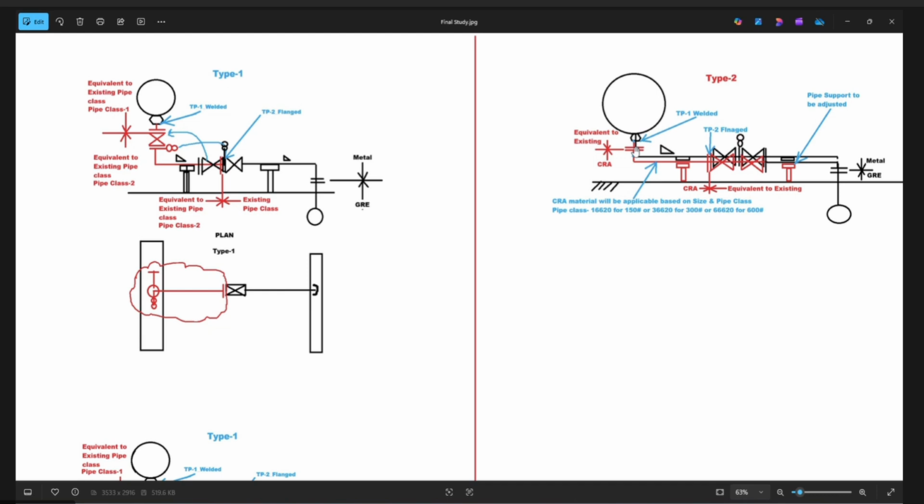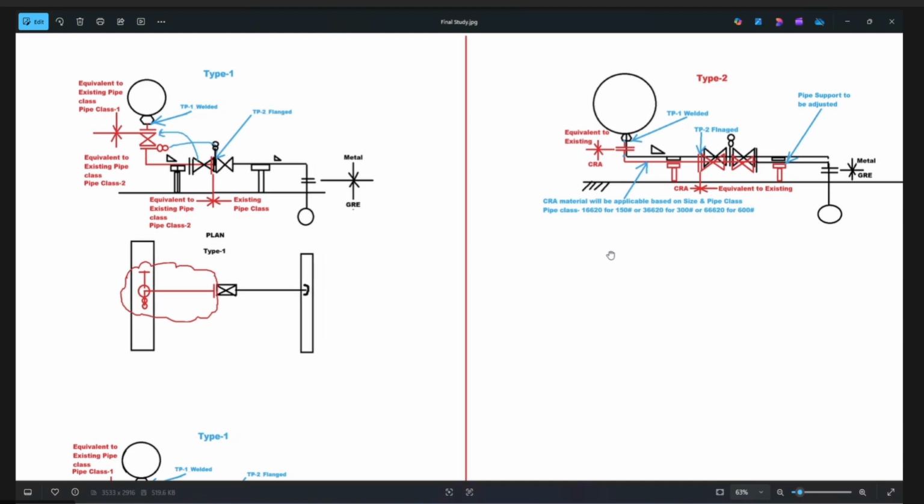But some drain lines we can avoid the plant shutdown. Even line shutdown is sufficient for us. But because at every drain point we have to cut the line and add either flange or both cases flanges are required, after this weldolet. Then this problem will be permanently resolved.